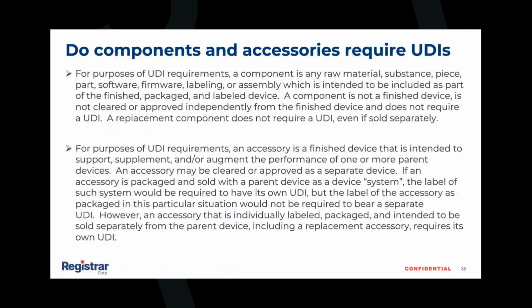Do components and accessories require UDIs? First, in the UDI system, we should define component. A component is any raw material, substance, piece, part, software, firmware, labeling, or assembly, which is intended to be included as part of the finished, packaged, and labeled device. A component as well as replacement components are not finished devices. They are not cleared or approved independently from the finished device. Therefore, they do not need a UDI.